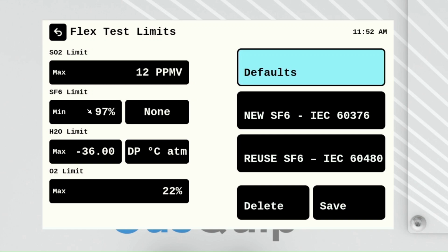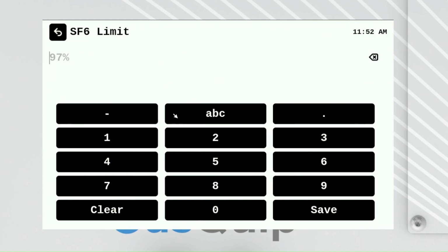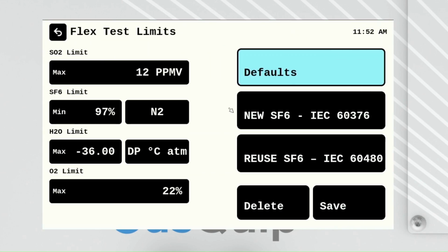The minimum is 97%, and if we toggle this to N2 or CF4, then we can also set the test limit minimum for SF6 for those individual mixtures. So if you had a mixture of SF6 and nitrogen, you can set this to whatever you want. And then you can also save a new value, and I can show you what that looks like.